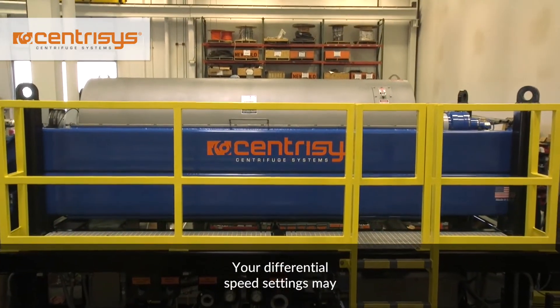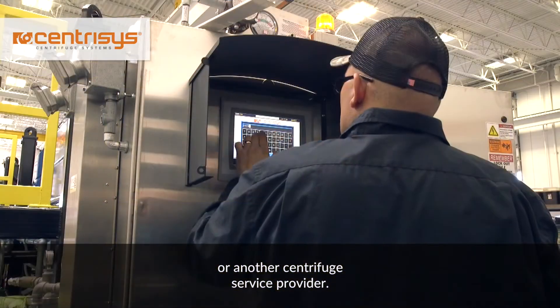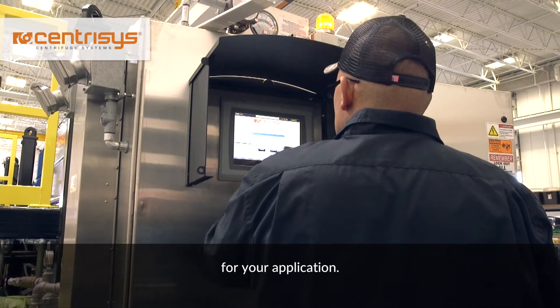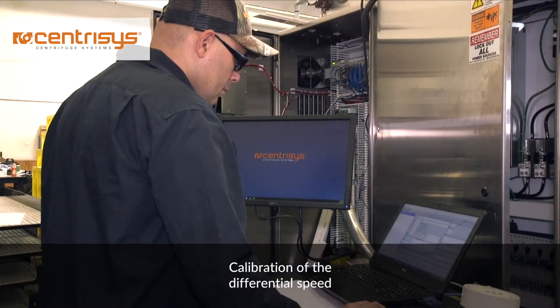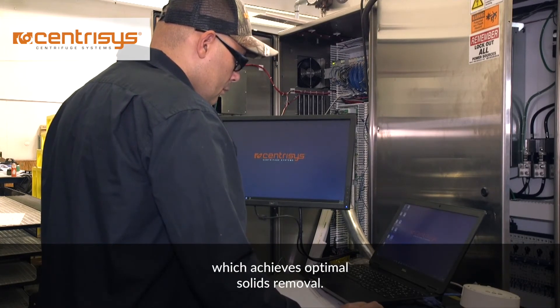Your differential speed settings may have been set initially by Centrisys or another centrifuge service provider. These are based on normal operating conditions for your application. Calibration of the differential speed ensures proper differential control, which achieves optimal solids removal.